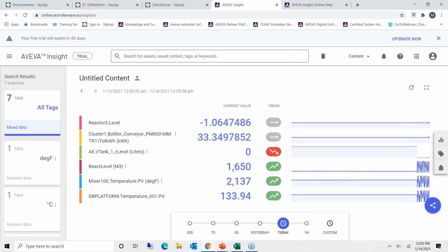But first, I will show you a live demo where I already prepared some data, or tags. The first tag here is connected through a CSV. This is manual data, and I'll show you how to create manual data or how to connect a JSON or IoT gateway. When you see the name of a cluster, that means this is a tag coming from a Citect SCADA. I have a tag coming from AVEVA Edge, another tag coming from InTouch, and another tag coming directly from OI Server. Here I'm using a Modbus OI Server, MBTCP. And last but not least, you can see the name of the PC or computer name, dot, the tag name. This one is coming from a Historian server.